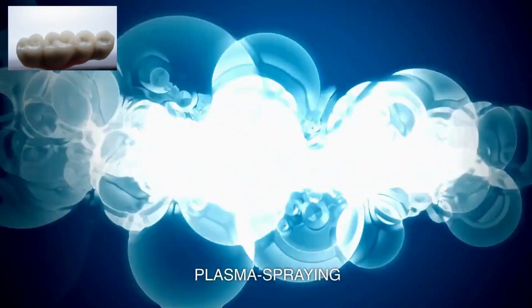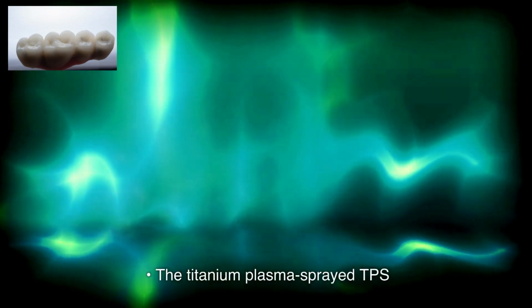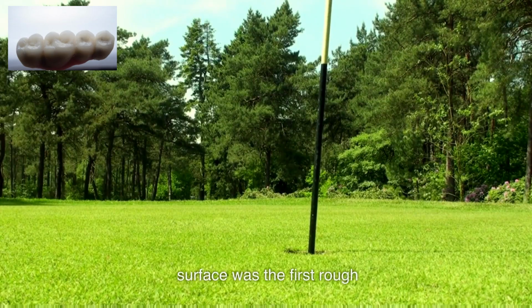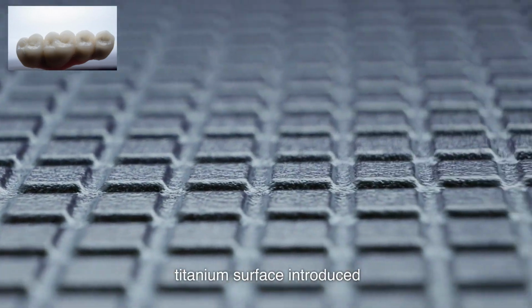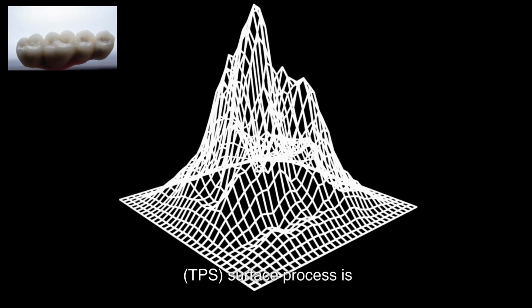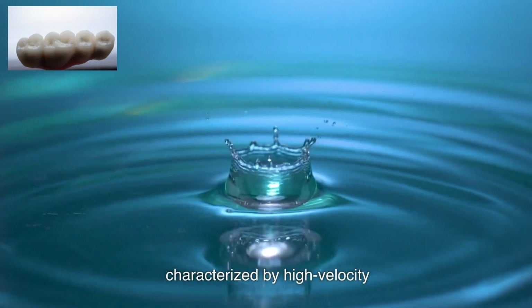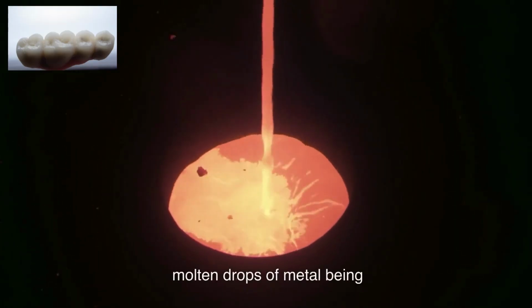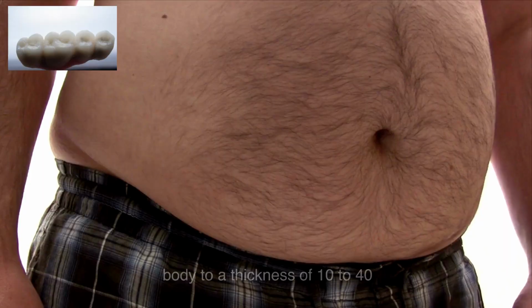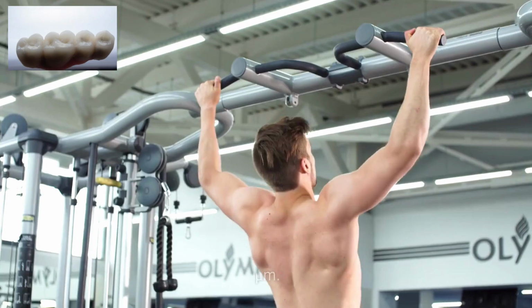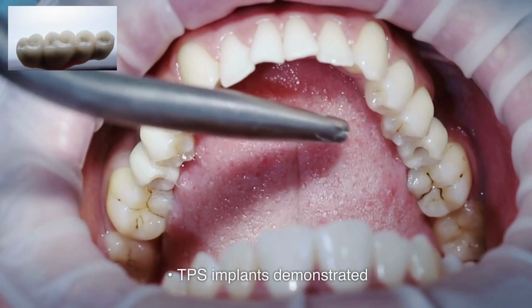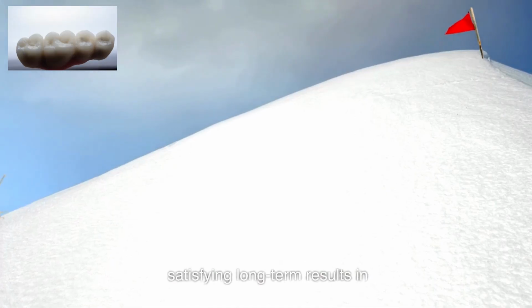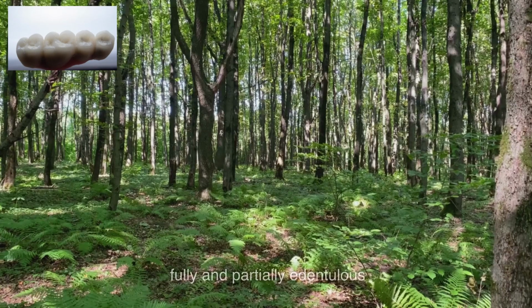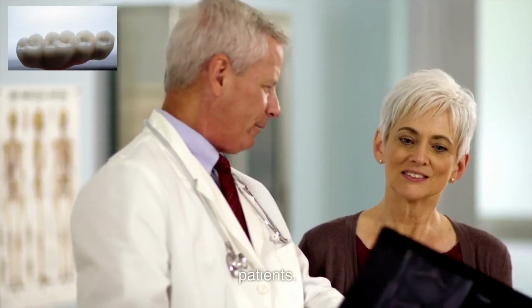Plasma spraying. The titanium plasma sprayed, TPS, surface was the first rough titanium surface introduced into implant dentistry. The TPS process is characterized by high velocity molten drops of metal being sprayed onto the implant body to a thickness of 10 to 40 micrometers. TPS implants demonstrated satisfying long-term results in fully and partially edentulous patients.